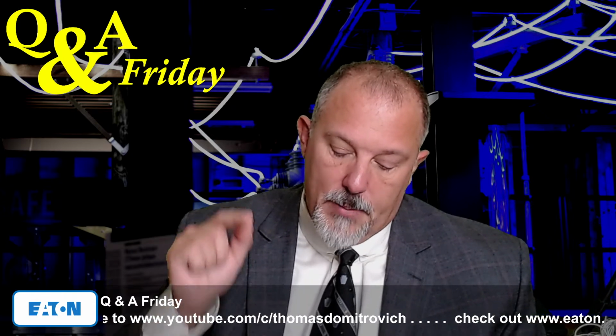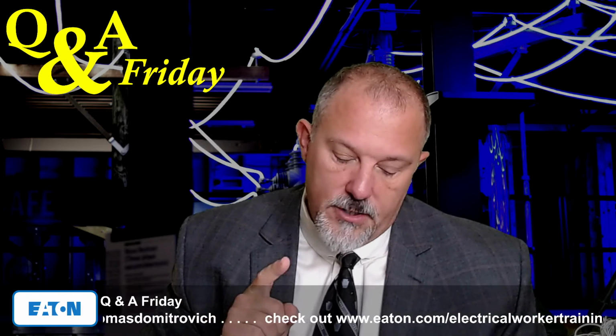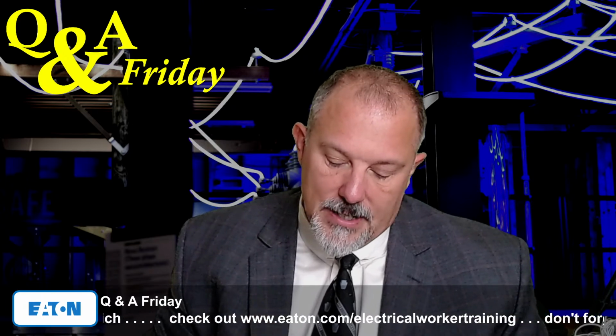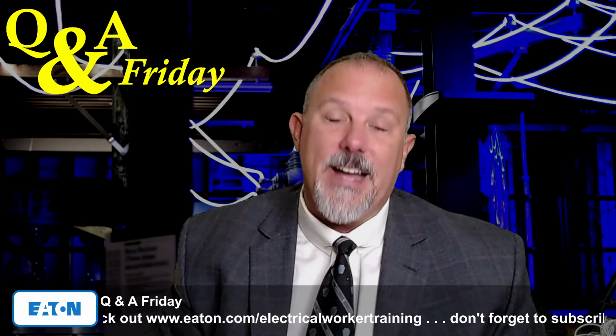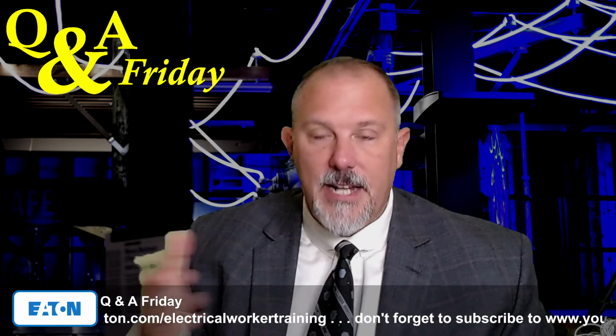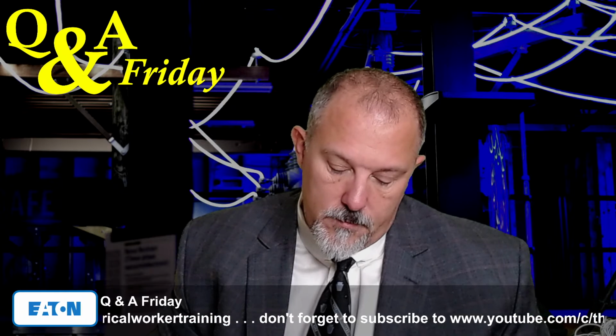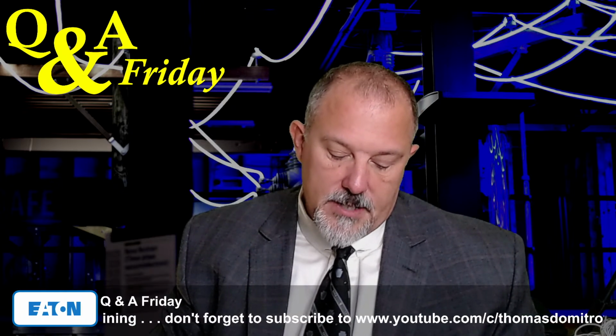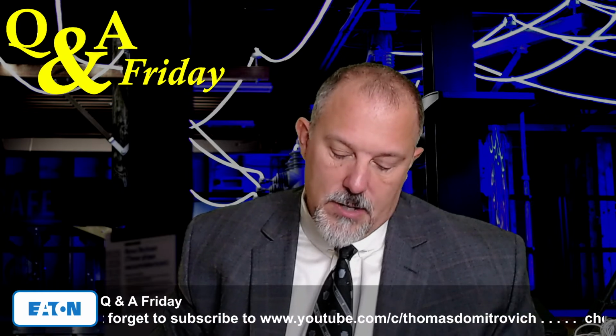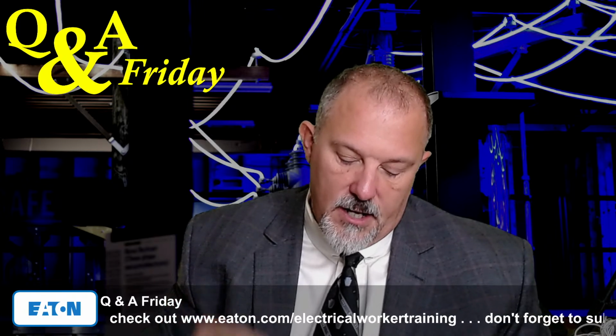It says the arc energy reduction protection system shall be performance tested by primary current injection testing or another approved method when first installed on site. The testing shall be conducted by a qualified person in accordance with the manufacturer's instructions, and you need to have a written record. But there's an informational note: some energy reduction protection systems cannot be tested using primary current injection testing due to either the protection method being damaged, such as with the use of fuse technology, or because current is not the primary method of arc detection.